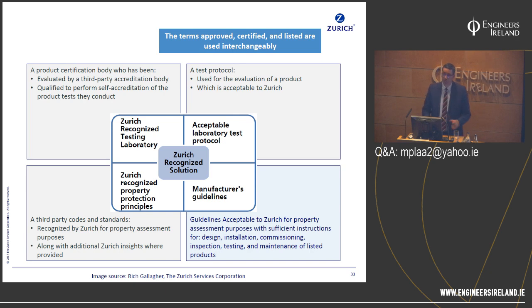So this four-stage process, I'll just elaborate on that now. So what's a recognised testing laboratory? It's evaluated by a third-party accredited laboratory. So it's a UKAS accredited or third-party independent laboratory, such as the BRE, the UL, for example, in the US. And have they got accreditation to undertake testing for water mist within their scope? So that's the first thing to check.